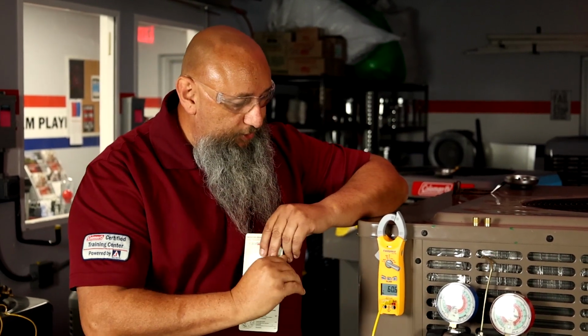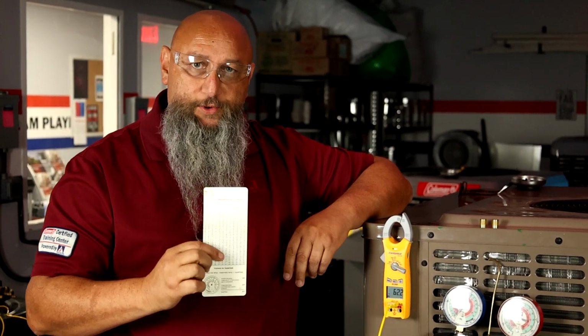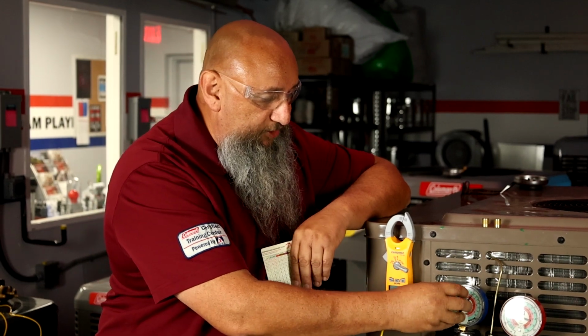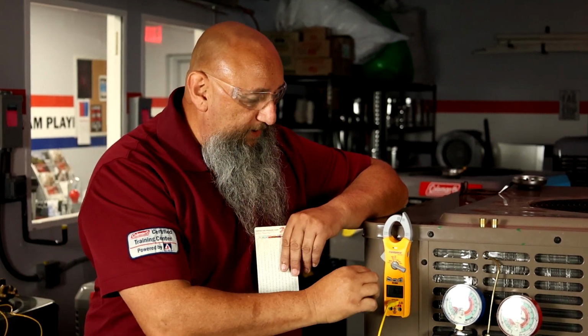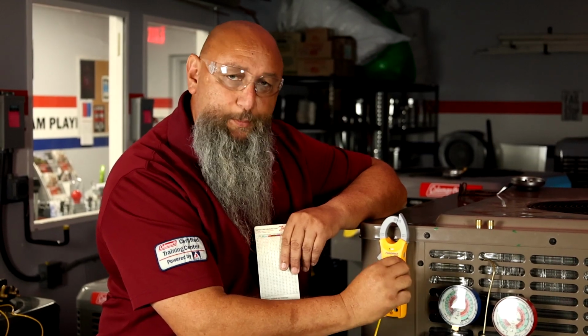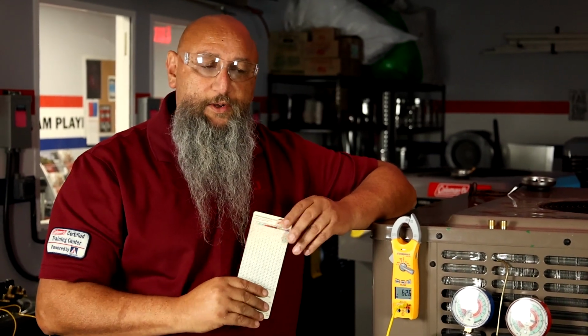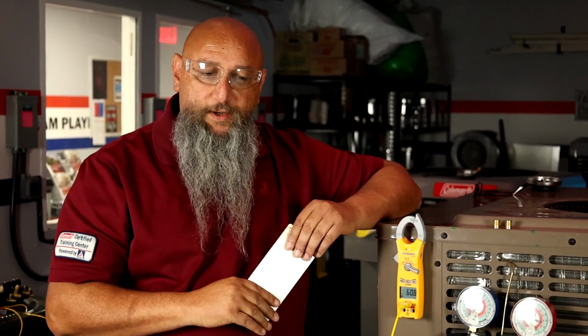In this case, what we just showed you was our pressure transferred to a temperature. And then we took a physical temperature reading. We subtract the saturation point from the physical temperature because we've heated that refrigerant beyond the saturation point. So if we take that physical temperature and we minus the temperature-pressure relationship chart, or whatever our saturation temperature is, that gives us our superheat number.